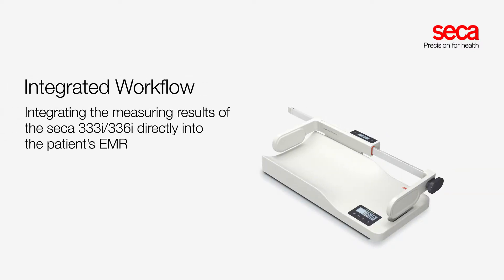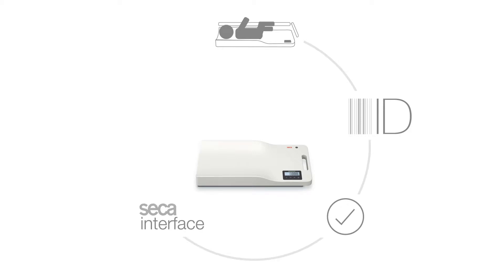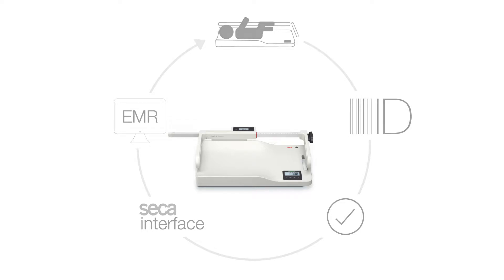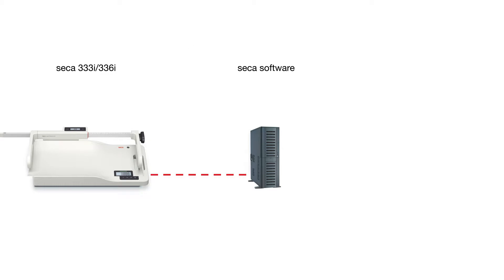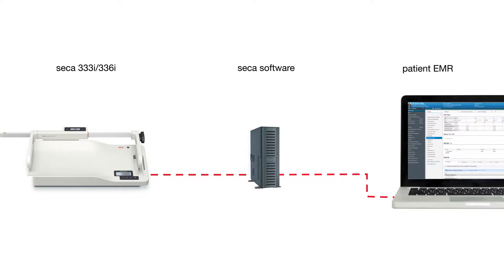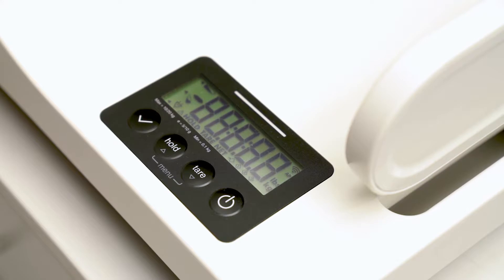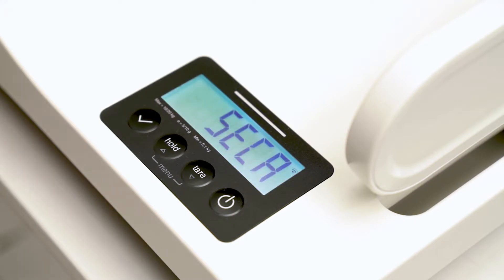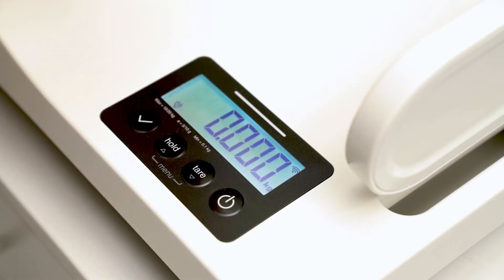This seca baby scale can transfer the baby's weight directly into its personal medical record in your facility's EMR system. With the optional digital measuring rod, the baby's length can be transmitted at the same time. When following a defined workflow, the measurements will be transmitted from the scale to a central server on the local network, on which the seca software will receive the data and relay it to the proper patient's record in the EMR system. The system is operational when the scale is turned on and the Wi-Fi symbol stops blinking.